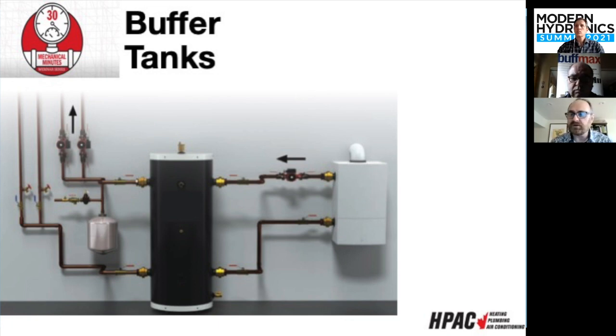So you don't jump into your car, or a truck driver doesn't jump into a big diesel truck, start it up, and drive off. If you notice, when they start them cold, they let them run to warm up and heat, because that's when they're going to run efficiently. A boiler works the same way, but in our systems, our boiler is designed to come on and off in response to loads. As a thermostat clicks on and a heat demand comes, the boiler comes on. And if the boiler is doing multiple things, it's probably going to be oversized for just one little job. So the boilers will come on and go off very quickly.